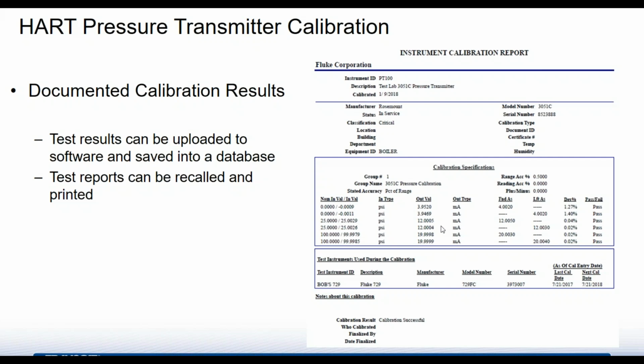And then another important thing is the auditor is also going to want to know, well, what about the test instrument you used to do the calibration? Well, that information also can be stored in the software. So in this case, I used a Fluke 729 to do the calibration, and you can see, at the time the calibration was done, it was within specification and in tolerance. So that's the kind of thing that auditors look at, and this is all protected. You can save the information as PDF files in your database. You can print reports out in multiple formats and access that information as needed.